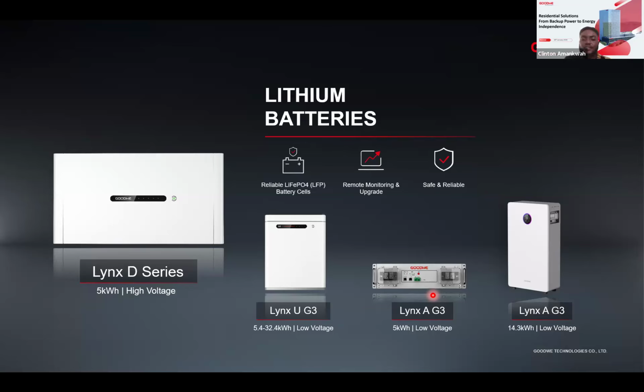One of the key benefits of using the GoodWe battery with the GoodWe inverter is remote monitoring and upgrade. Whenever you have GoodWe low voltage inverters installed with GoodWe low voltage residential batteries, for BMS firmware updates on the battery side, we take away the stress of having to walk all the way to the site just to do a firmware update. Instead, you get the flexibility to remotely perform your BMS firmware update through the inverter, which takes out the stress and makes the work much easier.